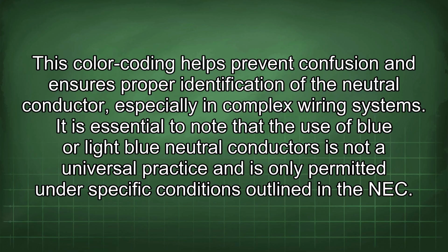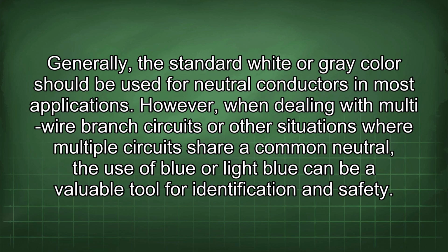It is essential to note that the use of blue or light blue neutral conductors is not a universal practice and is only permitted under specific conditions outlined in the NEC. Generally, the standard white or gray color should be used for neutral conductors in most applications. However, when dealing with multi-wire branch circuits or other situations where multiple circuits share a common neutral, the use of blue or light blue can be a valuable tool for identification and safety.